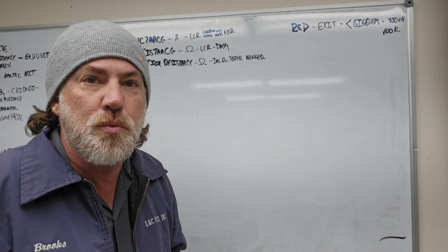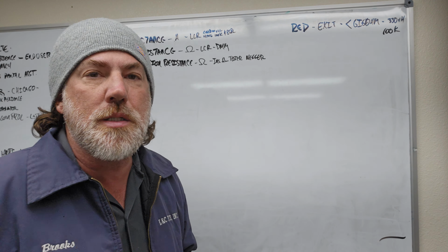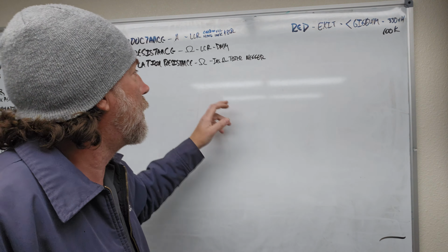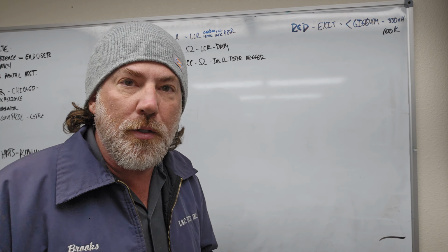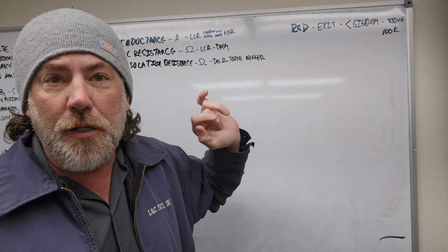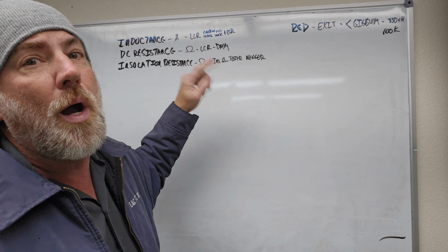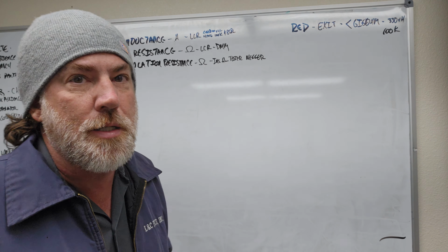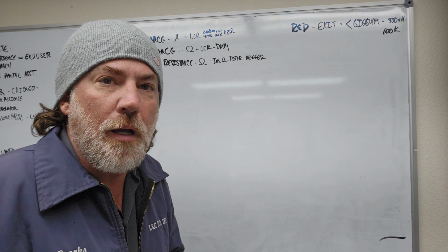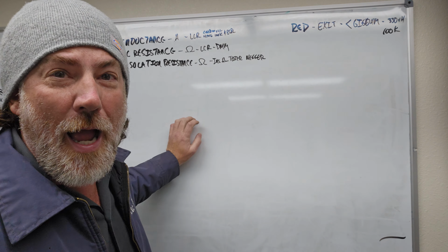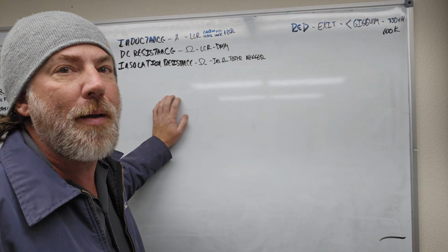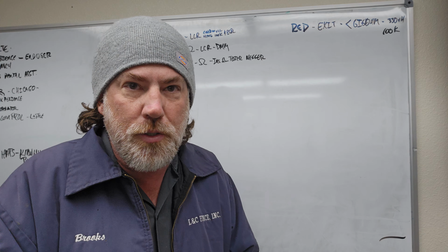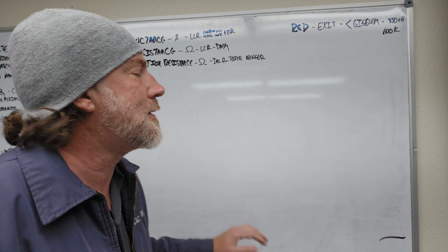Most digital handheld multimeters will be able to put a couple of volts out and tell you what the DC resistance is in ohms. The omega symbol is what we use in the algebraic formulas for that. And you can use an LCR or DMM to do that. So if you're using an LCR to test your inductance of the loop, why wouldn't you just hit the button to select from LC to R and go ahead and test the DC resistance? Well, I don't know why, but apparently Ruben thinks that this is an issue. I would say highly recommend doing that, because again, we're going back to that testing just insulation alone. If it tests good, doesn't mean that you actually have a good loop, which is why you would want to test the DC resistance on this.